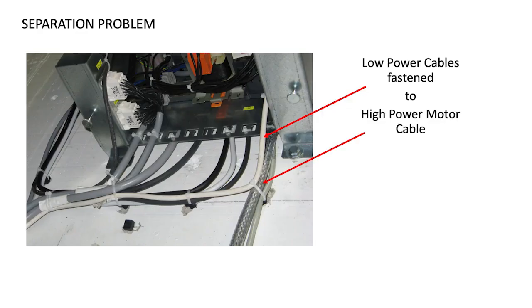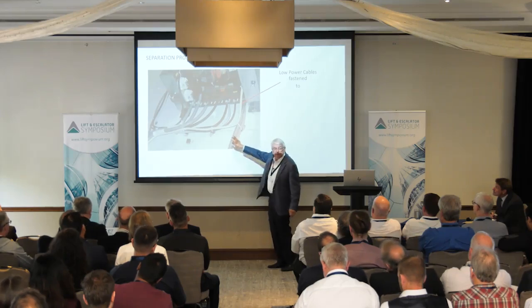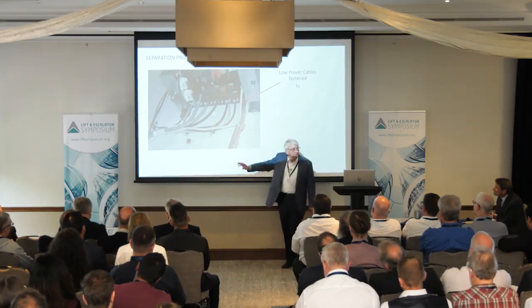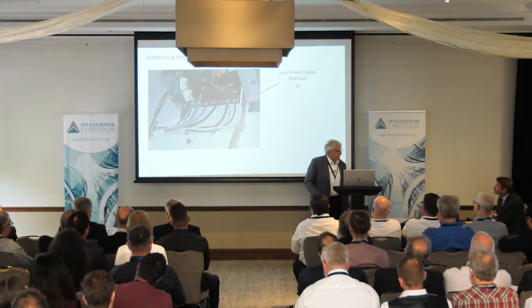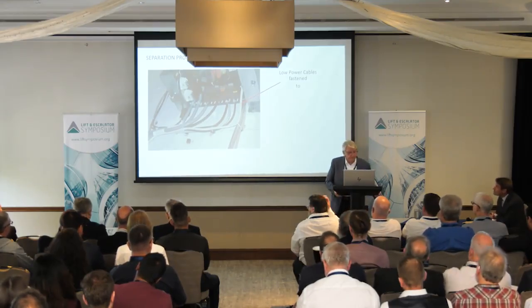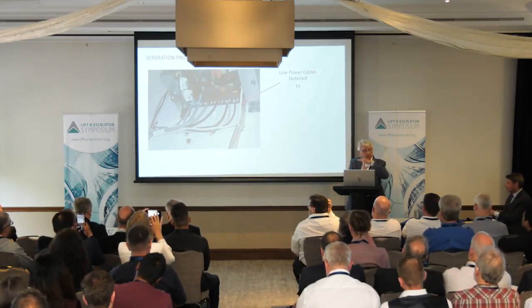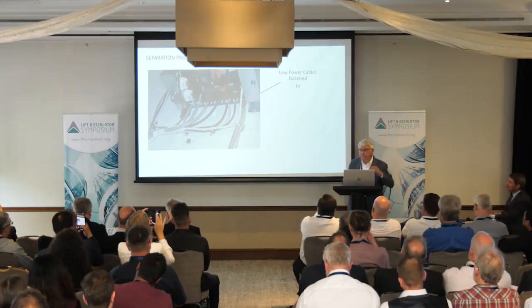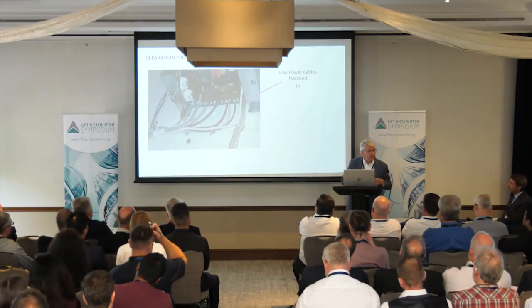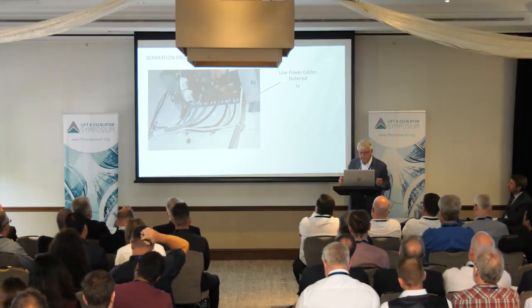So here's a variable frequency drive, and what you can see in this picture here is that the encoder low power wiring is strapped to the high power wiring. This is absolutely what you want to avoid doing, because that will create a lot of interference. If the wires have to cross, they need to cross at 90 degrees, so that you have the minimum amount of conduction and induction.